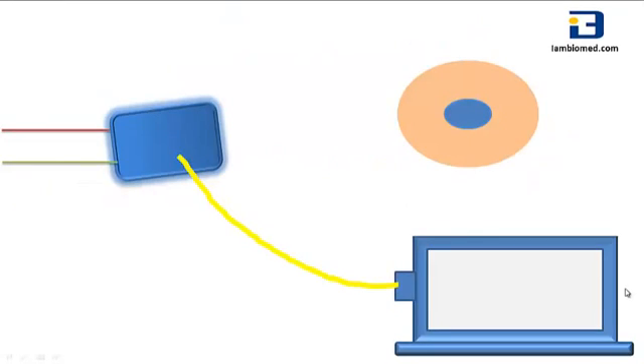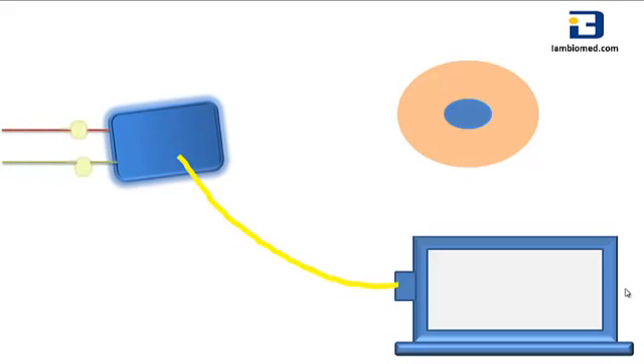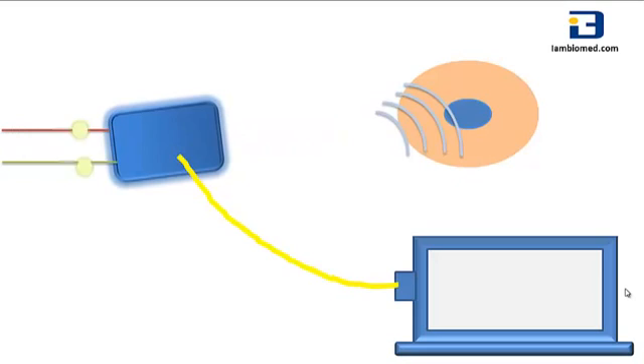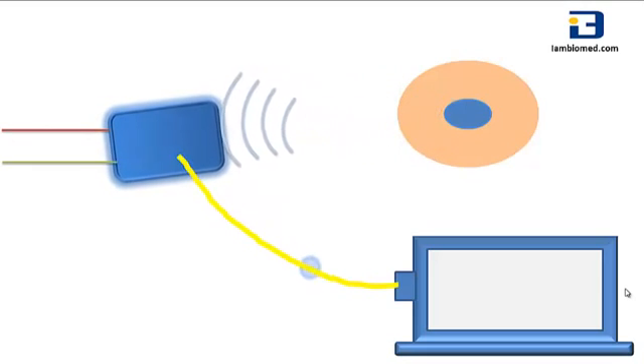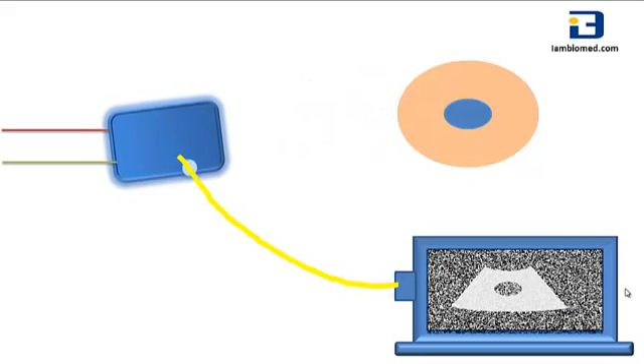The illustration shows how ultrasound works. The system consists of a transducer with a piezoelectric crystal — when electricity is applied to it, the crystal shakes and ultrasound is emitted. The sound waves then travel into the body. The waves are reflected back to the probe and the crystal shakes again, transducing the acoustic energy back into electric energy, and then the machine plots the image on the screen.